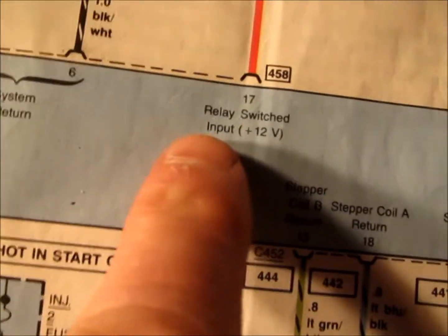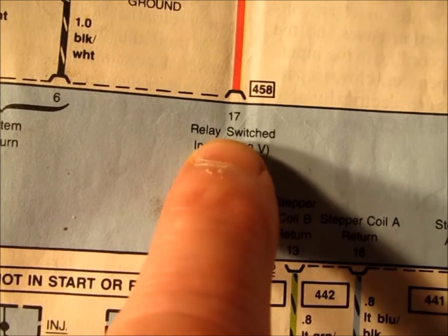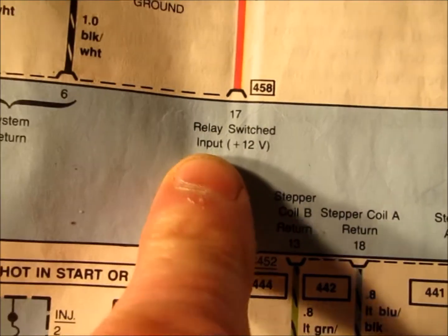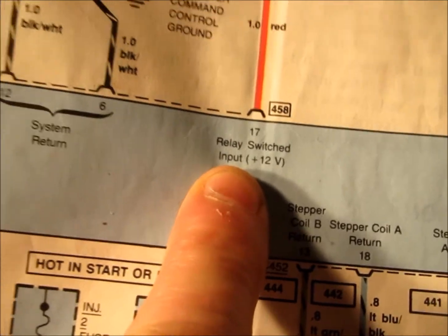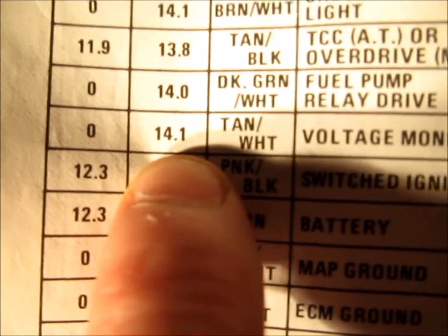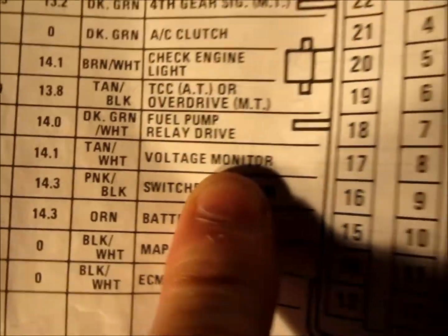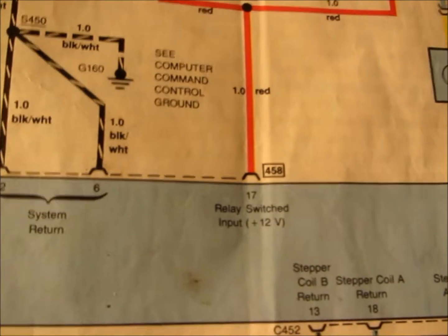If you look at pin 17 of the electronic control module, that's a relay switched input for the relay. And pin 17 is showing 14.1. It's a voltage monitor. If it doesn't see the voltage that it wants to see, it's just going to shut things down.